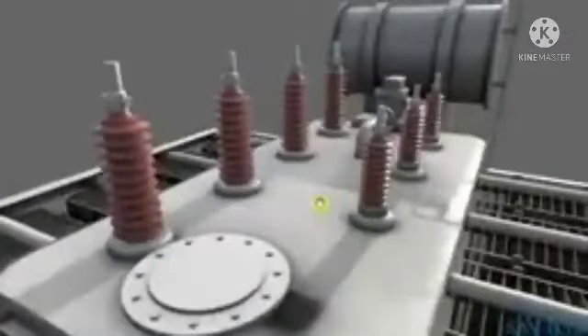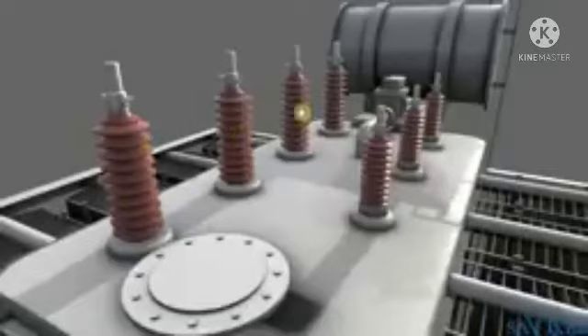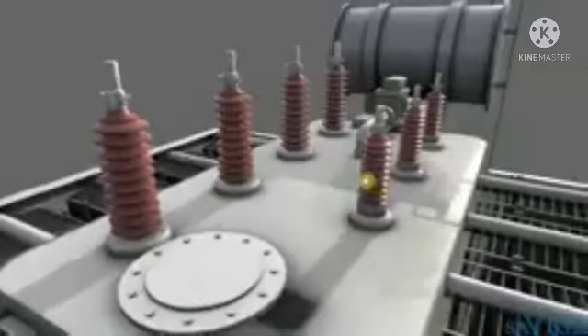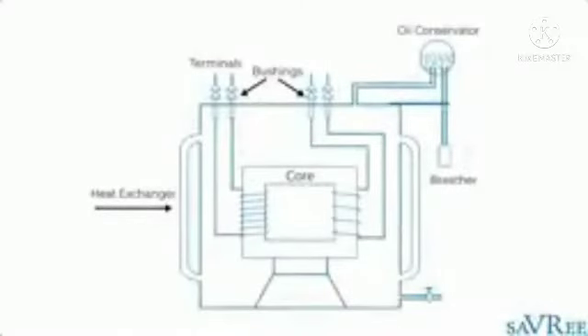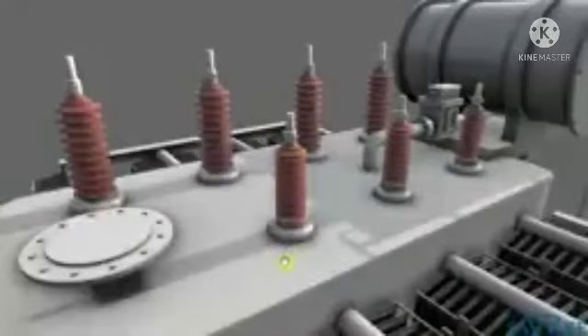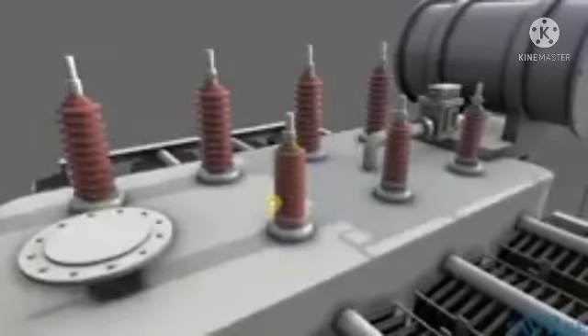We can see the bushings passing through the transformer casing and pointing upwards. As you can see on the left side, there are 4 high voltage bushings and 3 low voltage bushings. The high voltage bushings have more insulation and the low voltage bushings have less insulation. The purpose of the bushings is simply to connect the internal windings of the transformer to the outside electrical circuit. And we want to do this without raising the electrical potential of the tank itself. And that's what the bushings allow us to do. They allow us to pass the cable through or to connect the electrical circuit from the inside to the outside without raising the electrical potential of the transformer tank itself.